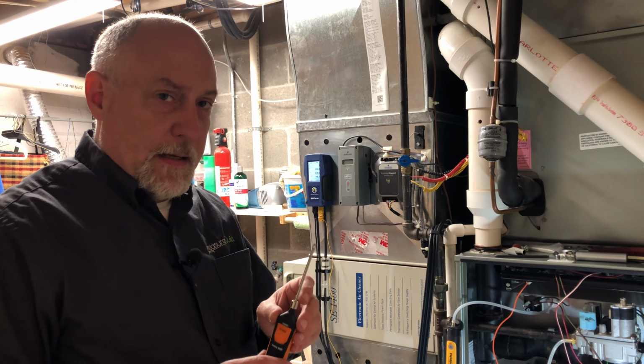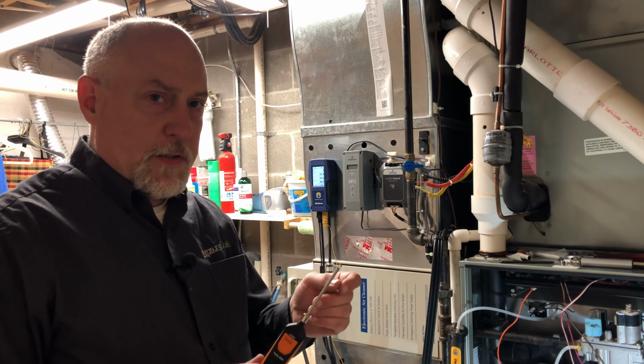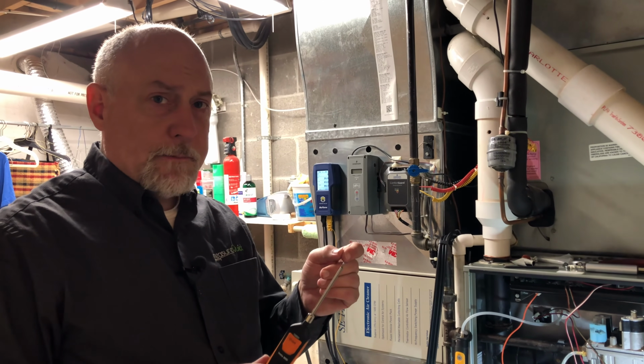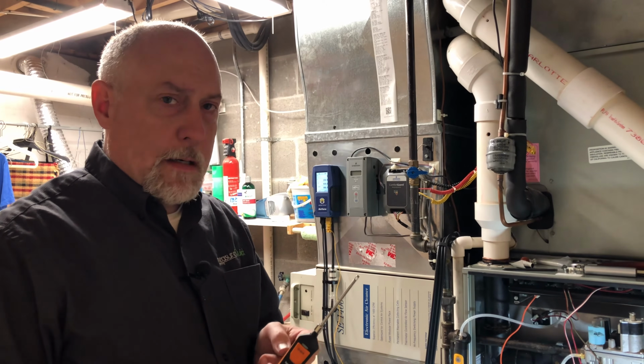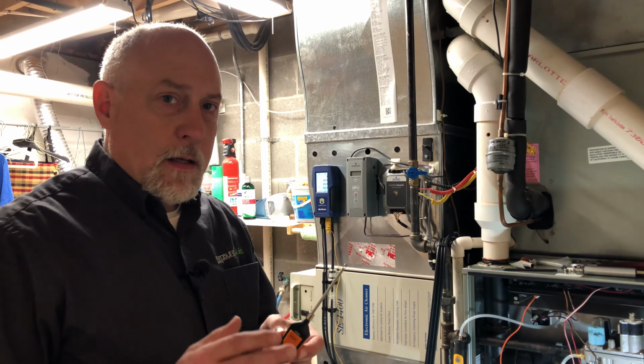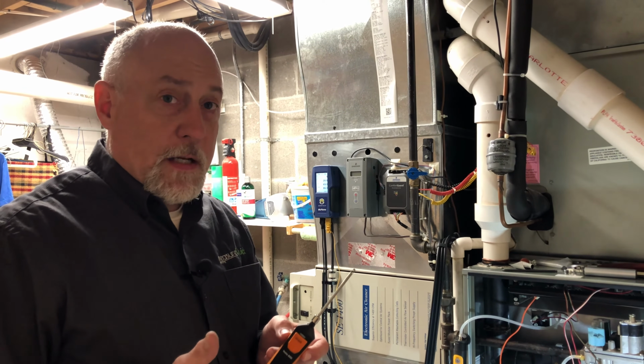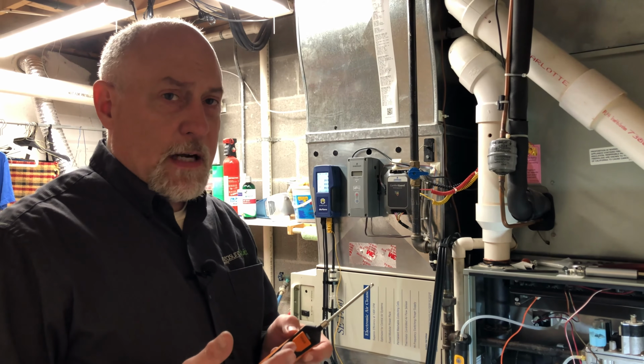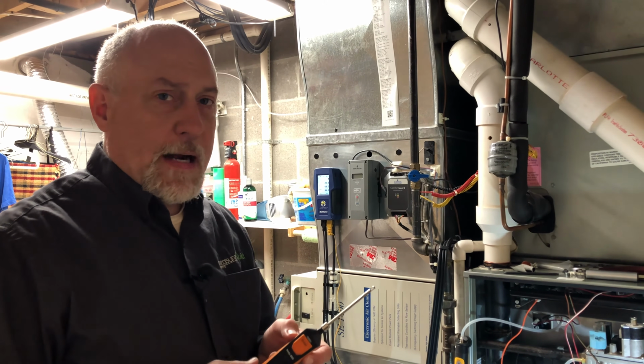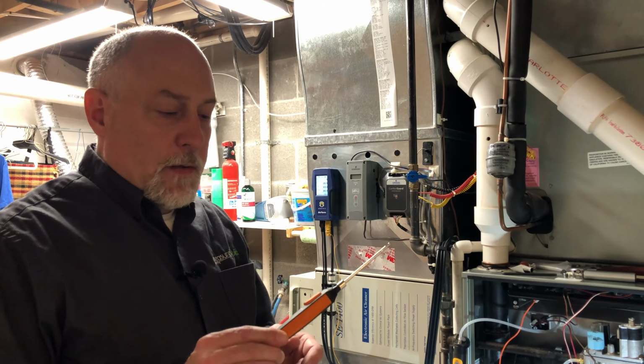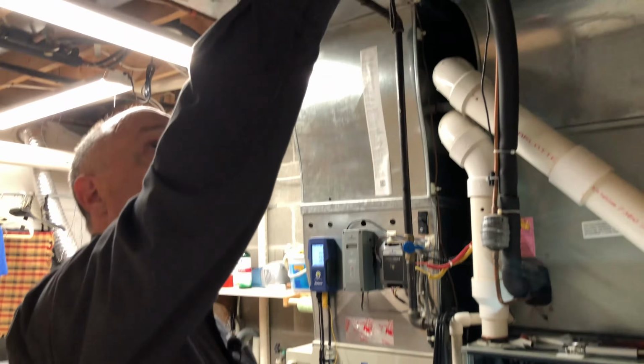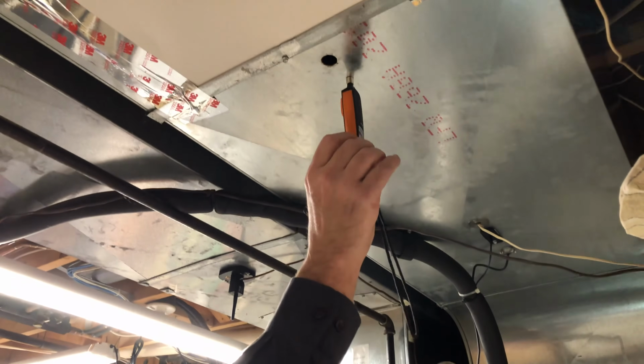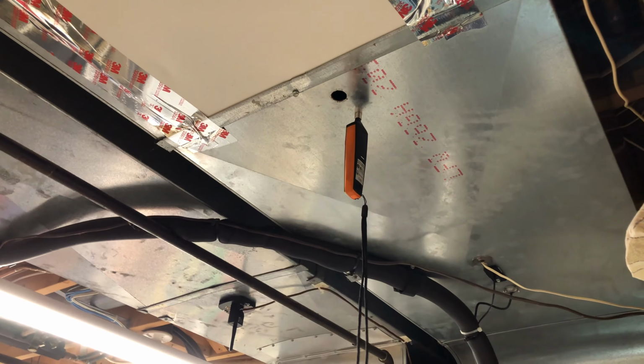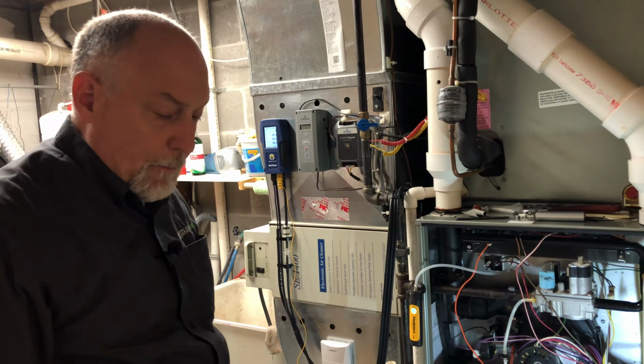The FieldPiece and the Testo humidity sensors are rated at 140 degrees, which for a lot of humidity sensors is too low for a furnace. The other thing is that in that hot air, it dries the humidity sensor out and it'll compromise your accuracy. So you really should go with a Testo 905i for that. We're going to go ahead and stick that up here in the supply duct. I put a little magnet on mine to make it stick in there. And now we've got everything sort of paired up and ready to go.